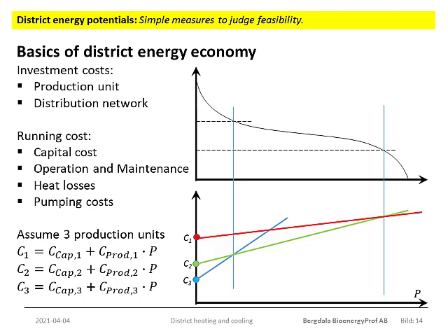The amount of energy may be small from unit 3, but the power delivered is high. So this is the cheapest one to use for high load. The green curve for unit 2 is the optimal for use during spring and fall. And unit 1 is the best one for summer load. Again, the amount of energy delivered is small, but for summer load the power demand is also low.